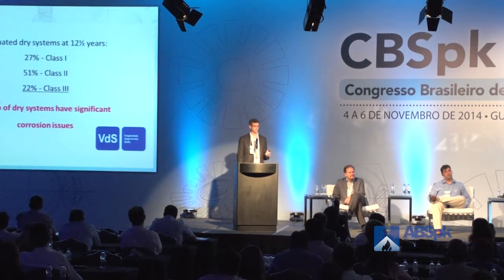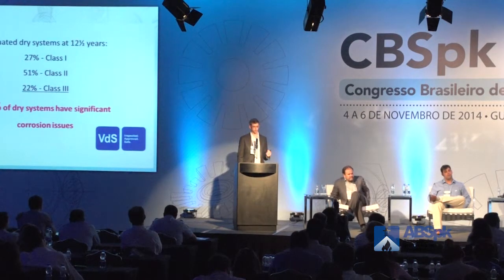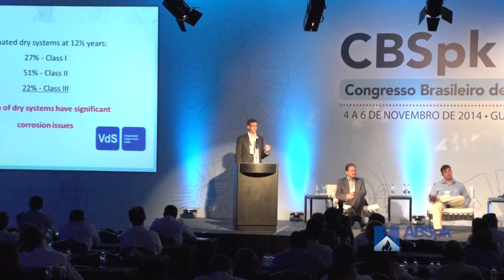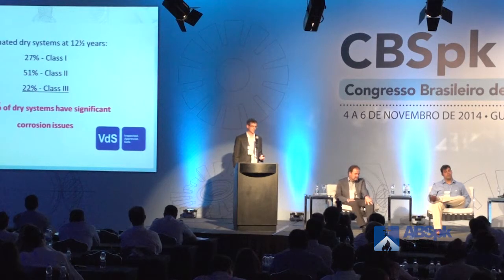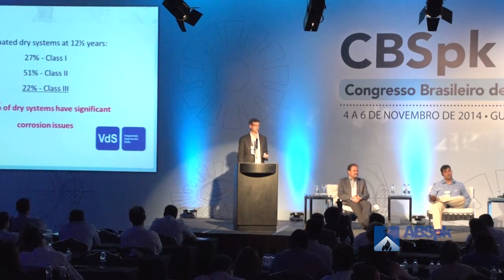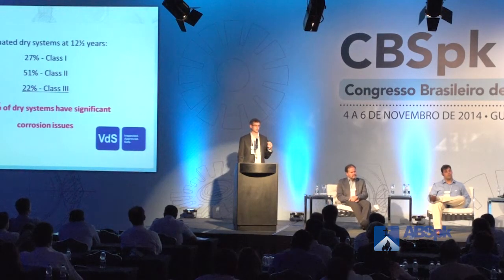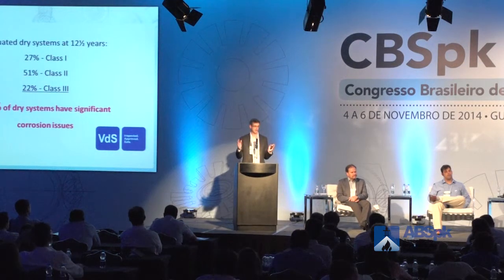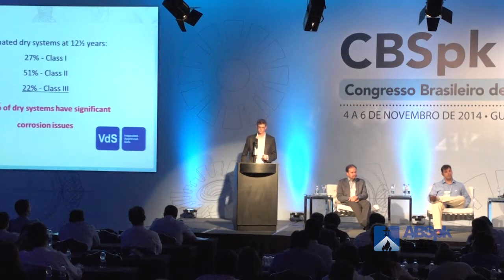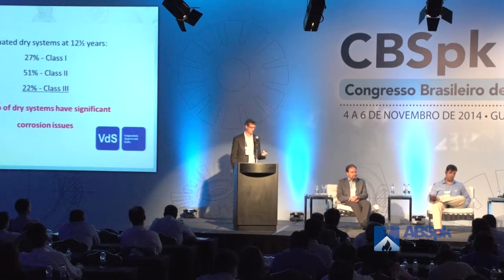So the results of dry systems were even worse. They couldn't even expect dry systems to last 25 years. They actually had to shorten it to 12 and a half years because of so much corrosion going on. 73% of dry systems, after being installed for 12 and a half years, had to have corrosion replacement. So they had to replace sections of pipe or the entire piping system, again, at a cost to the building owner.